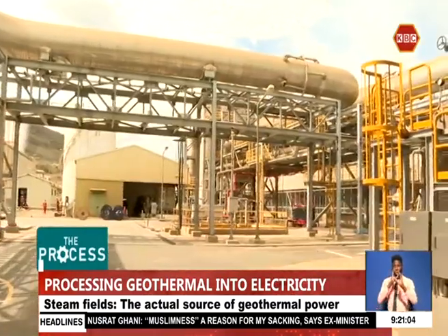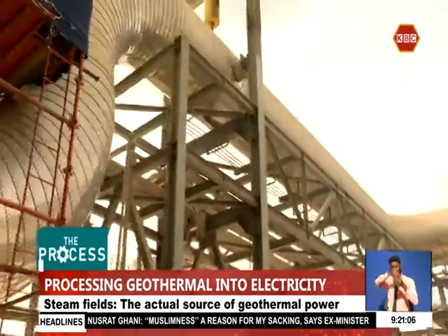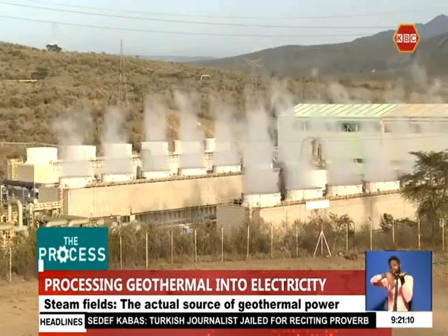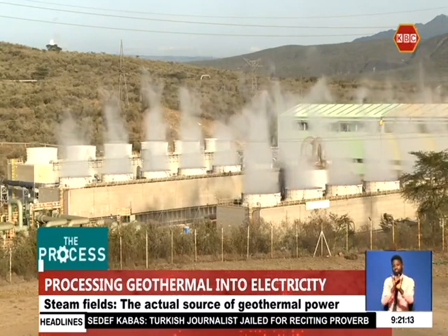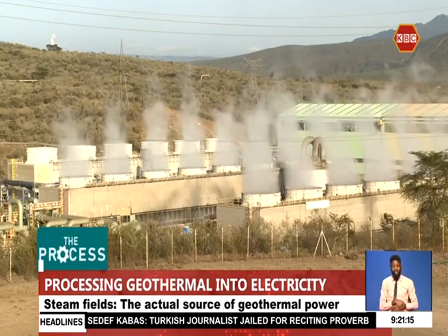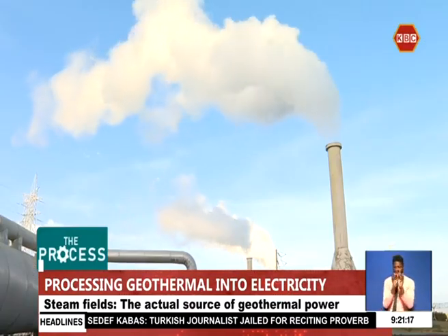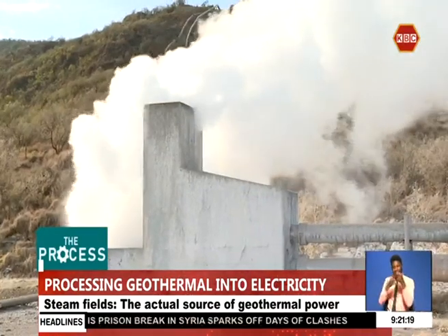Once the steam is at the plant, it goes through a steam scrubber, the objective being to remove any water that has remained or come with the steam. The steam must be 99.99% dry to operate the turbine safely.